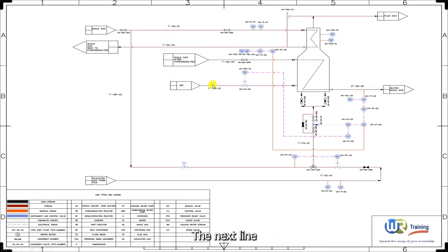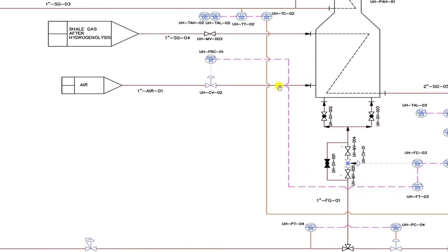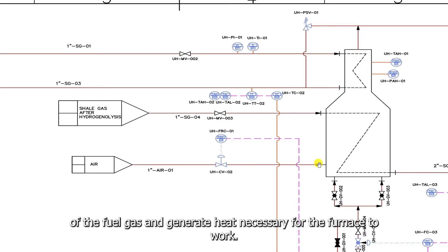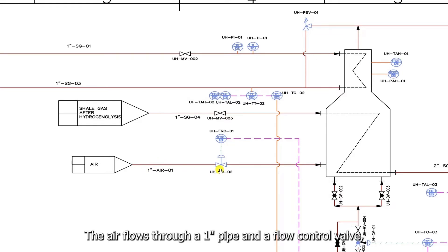The next line, that you can see here, carries process air. Air is admitted to the furnace to ensure the combustion of the fuel gas and generate heat necessary for the furnace to work. The air flows through a one-inch pipe and a flow control valve, tagged CV02. The air is then mixed with fuel gas and burned.